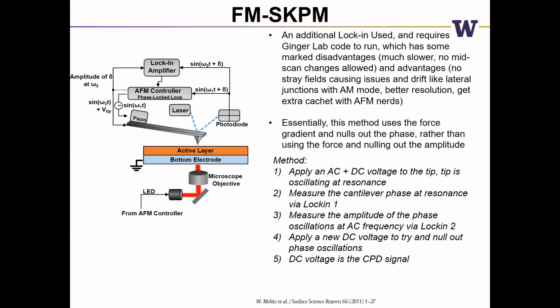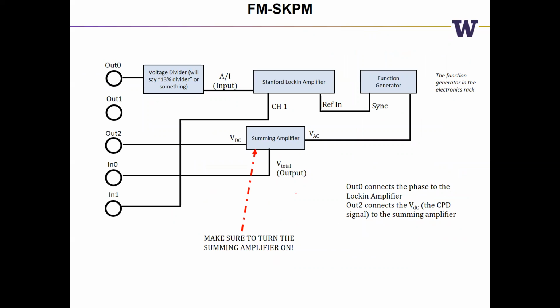And as a brief aside, to make sure that this is fairly exhaustive, I did write up some notes for people about how FM Kelvin probe works. You do need an additional lock-in. The reason to use frequency mode is that you have some notable advantages: you don't have these stray fields causing issues like you do in AM mode. You generally get better resolution because you're looking at the force gradient rather than the electrostatic force, and that's because you're trying to null out the phase. And again, like on the previous slide, I wrote out the method in step-by-step fashion for AFM students to go through at some point, or to keep in mind. And similar here is for when you actually want to set up the experiment. This actual diagram is printed out and pasted on the MFP3 chamber as well. I think that one's in better colors than this, but it's the same diagram.